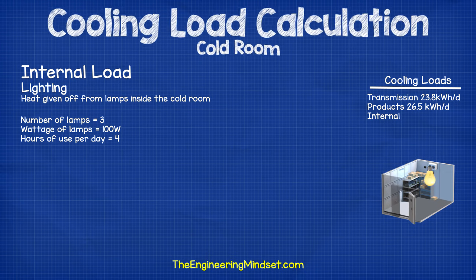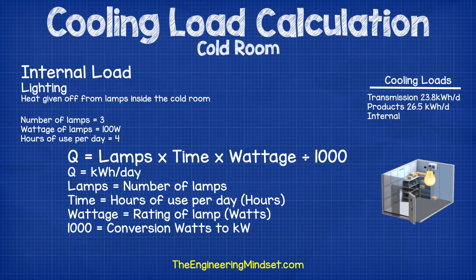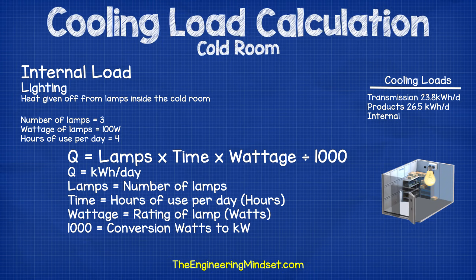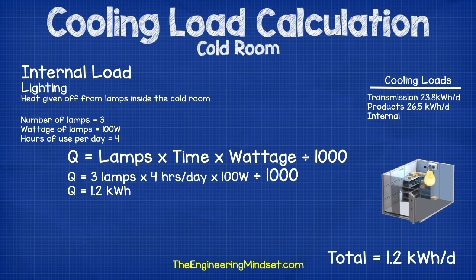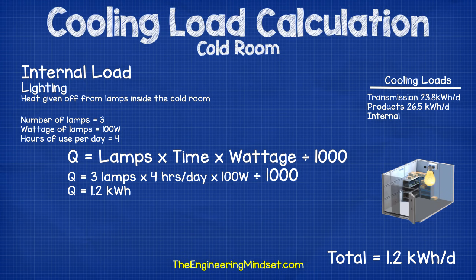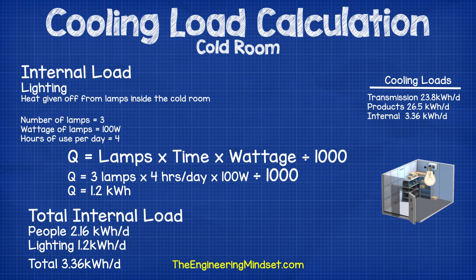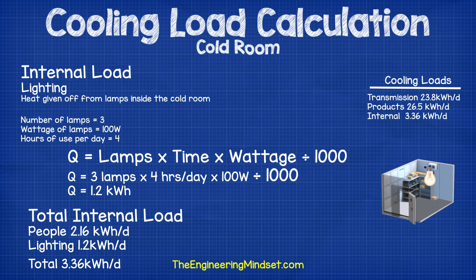Then we calculate the heat generated by the lighting using the formula q equals lamps multiplied by time multiplied by wattage divided by 1000, where lamps is the number of lamps, time is hours of use per day, and wattage is the power rating of the lamps. With three lamps at 100 watts each running for four hours a day, these give off around 1.2 kilowatt hours of heat per day. Summing the people and lighting loads gives a total internal load of 3.36 kilowatt hours per day.